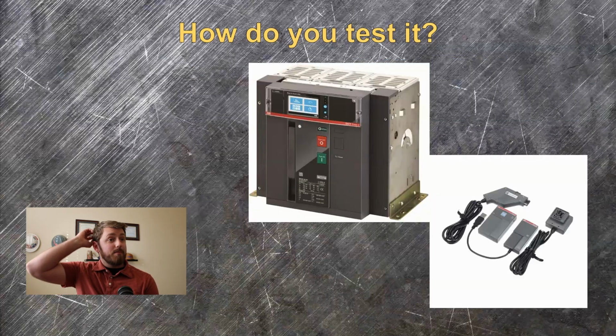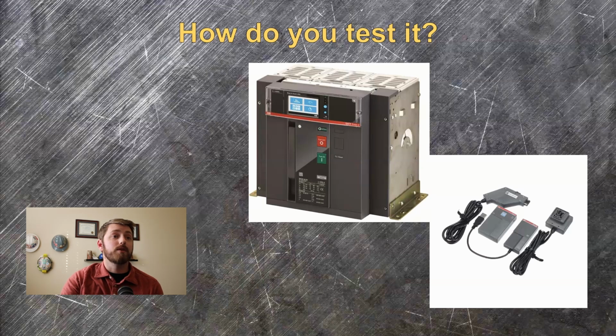The ABB EKIP is the only one I can think of where you can turn it on without an external power supply. So if you're bench testing it, it would be theoretically okay to enable it, to test it by enabling RELT through the EKIP Connect software, assuming you have the $500 USB adapter that they made you buy. Again, you haven't proven it works until you both trip the breaker at the maintenance mode setting and prove that you can turn on maintenance mode with the maintenance mode switch in the gear as it sits. If you don't do both, you're doing it wrong.